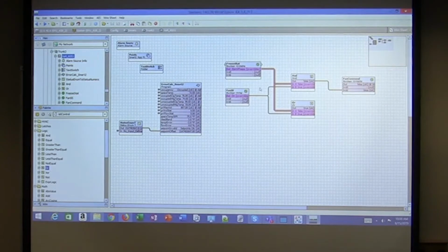There he goes. So now we got a freeze alarm because we're telling it to run based on the start stop. Freeze not good anymore. So now it kills the fan and shuts us down. So we're taking these logic blocks to link all this stuff together, to tell it to do a function and do something, right? So you're going to see ands and ors and different blocks.